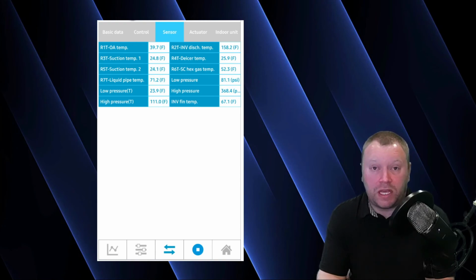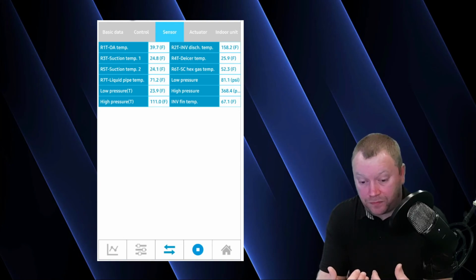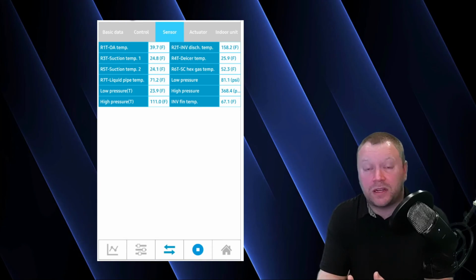And in that particular case, I took runtime data all day long, because as we slowly dialed in the refrigerant charge, it takes time. And that is the most important thing that I could probably stress to you guys when you're looking at runtime data: you have to be patient. And I'm the most impatient person, so it's very hard. I totally understand. But you have to be patient. You have to let the system have time to adjust and come to its targets and give it time to react, because you can't add or remove and then immediately see the difference. It's going to take a few minutes.